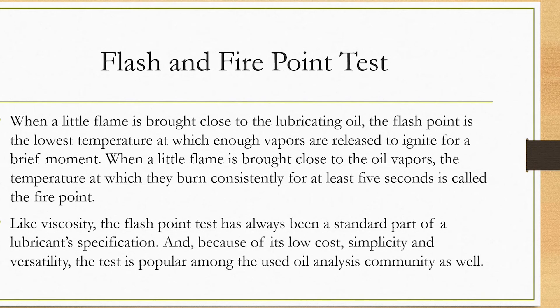In the flash and fire point test, we find the temperature where there will be a brief moment of ignition, and the temperature where there will be consistent burning for at least 5 seconds. The procedure involves heating the fuel or oil, then lighting the vapor above it — not the fuel directly. If nothing happens, we continue heating. When it briefly ignites, that is the flash point. When it burns consistently and sustains the fire, that is the fire point.